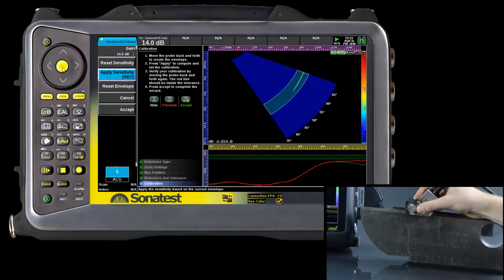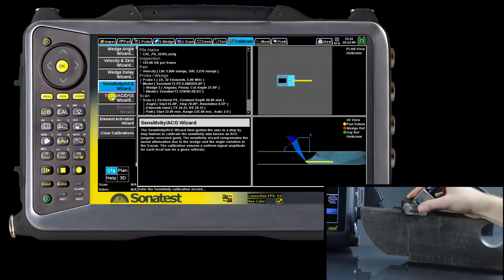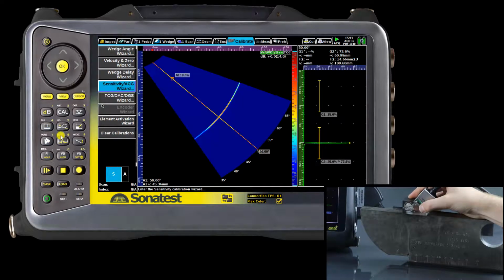We can now see that the signal for the 60-degree angle is slightly off tolerance. If this occurs, we need to sweep again the reference and reapply the sensitivity correction until the signal is within the expected tolerance. Once the wizard has been completed successfully, we can confirm that the signal amplitude response is 80% for all angles once maximised.